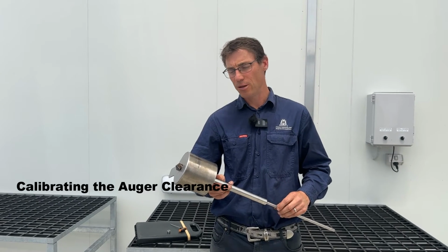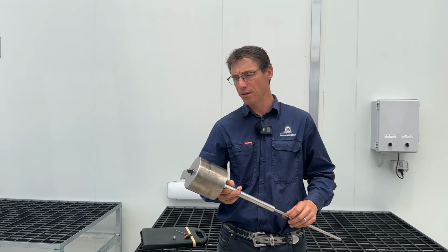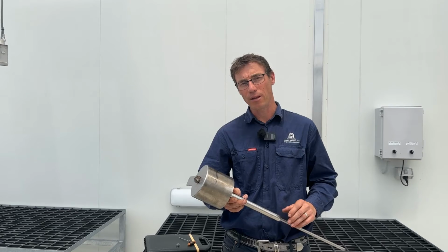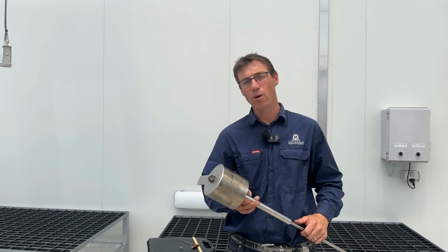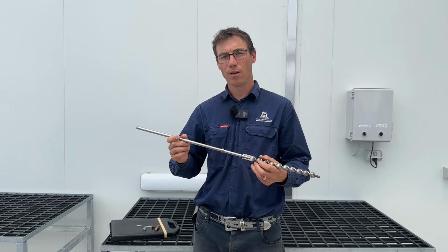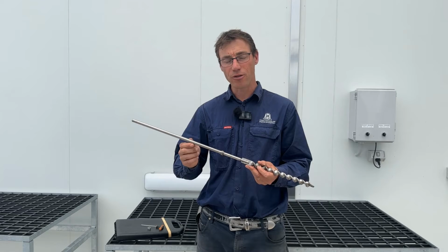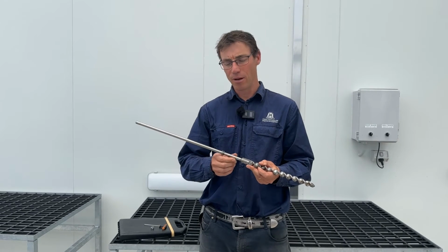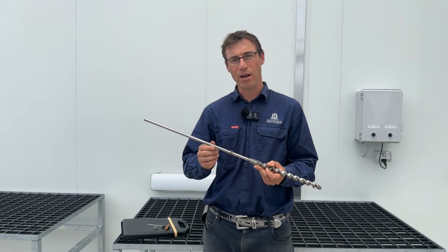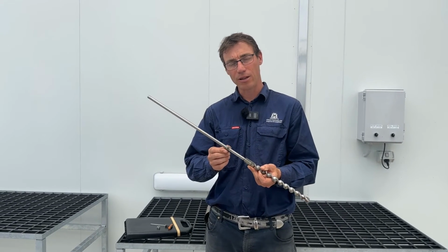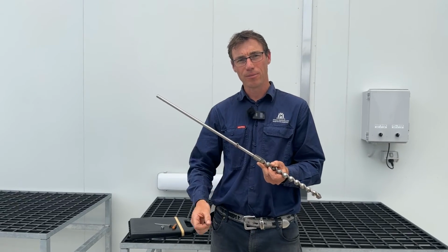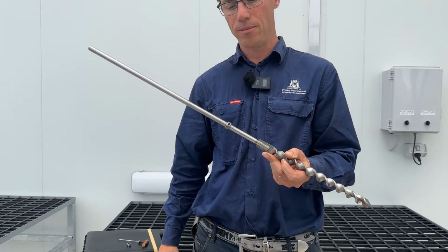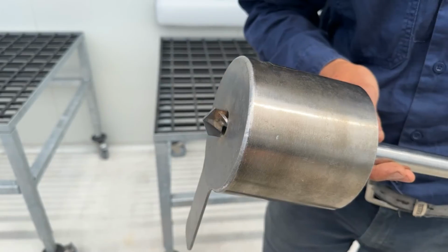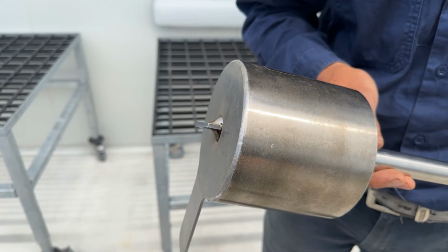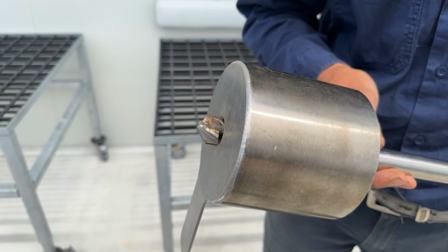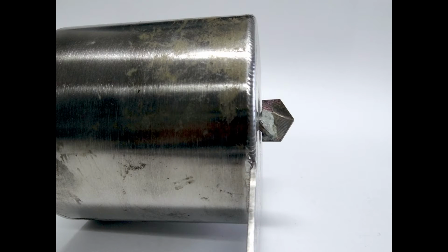The first step is to calibrate the auger clearance. This is to ensure that the tungsten tip does not wear away at the bottom of the bucket. The design of the spacer has now changed. Instead of a bit of PVC pipe, we now have a stainless steel collar with an Allen key. This collar can be moved to ensure there is a 1 to 2 millimeter gap between the bucket and the tungsten tip.